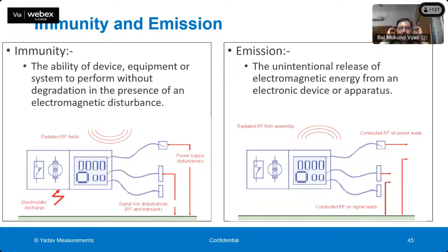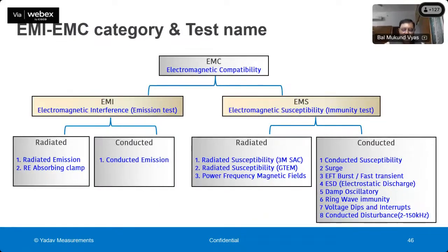The emission limits are typically specified in standards which are called CISPR. This standard series also works very closely with the IEC. The emission limits are specified in CISPR standards, and the immunity testing for various kinds of disturbances is specified in IEC standards. IEC has a very specific series of electromagnetic immunity disturbance testing, which is called the IEC 61000-4 series, and we will see this. So again, this is presented here.